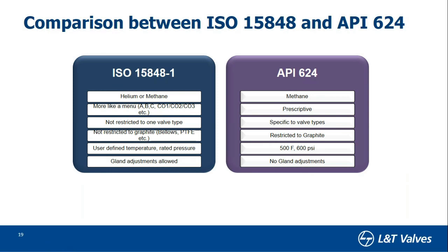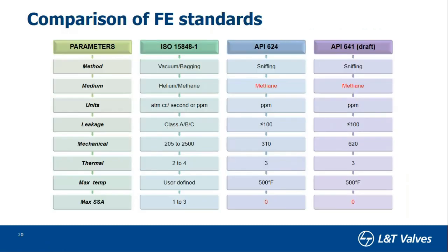In a gland packing, the gland nut is very important — it provides the loading or packing pressure that creates the seal. If the gland load is loosened, the media will start leaking. One way of arresting leakage is to tighten the gland nut — that is called gland adjustment. API uses methane gas; you measure the concentration of methane mixing in air — this is the PPM sniffing method. ISO measures both PPM and leakage rate using different specialized equipment for each standard.